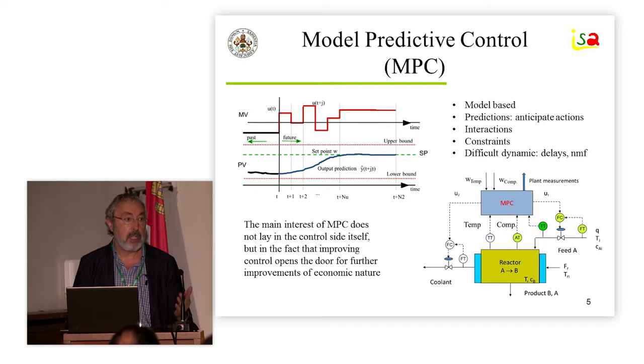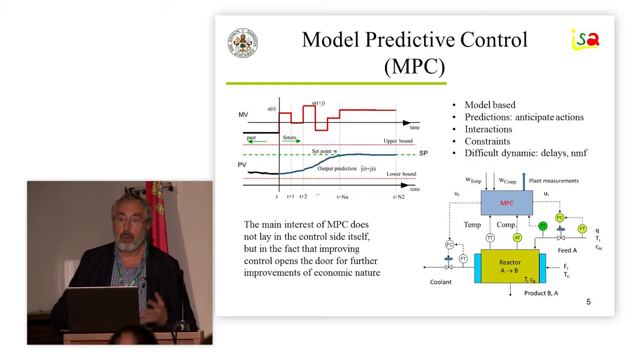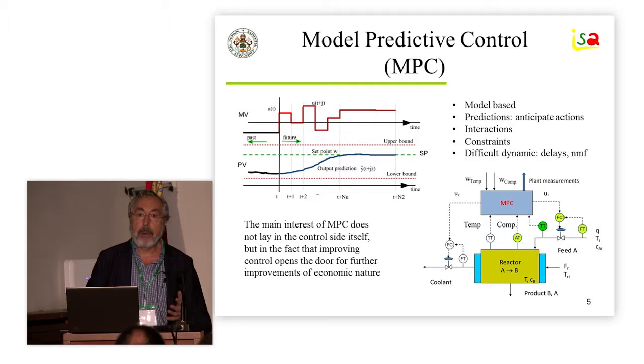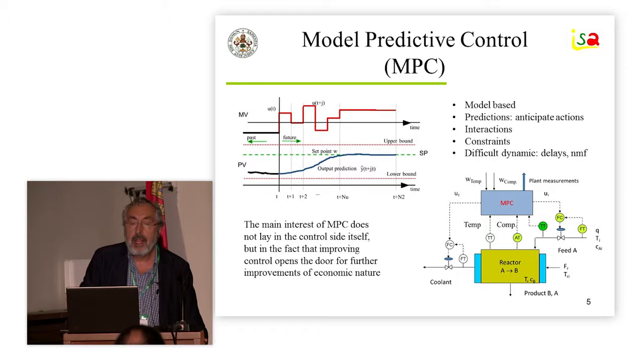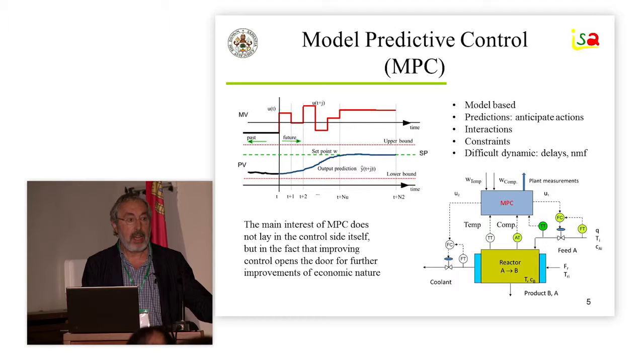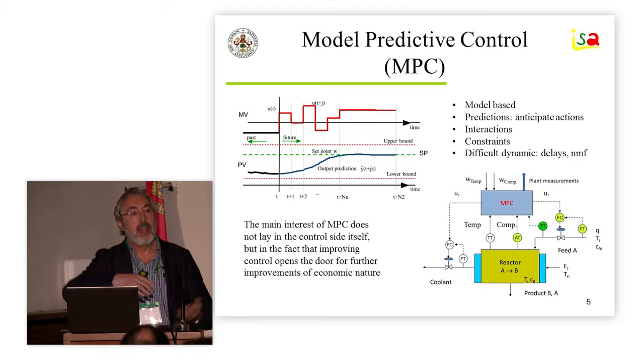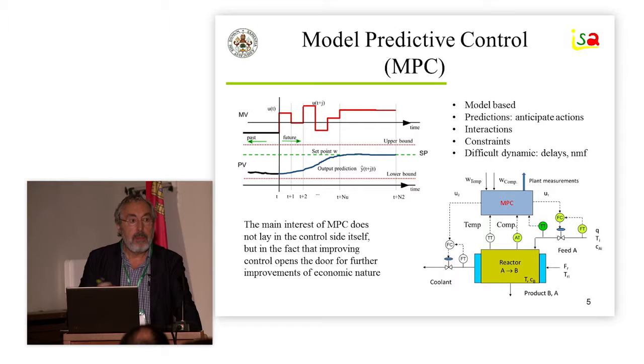The second step forward was given by the introduction of MPC. All of you know the fundamentals of MPC: you have a model in which you predict the future behavior, you can include the interactions between the different variables, and you can also explicitly consider constraints on the manipulated and the controlled variables. The quality of control clearly improved a lot — you were able to control the operation of a whole process unit, a distillation column, a reactor, and so on. The operators appreciate the fact that they don't have to worry continuously about the constraints.